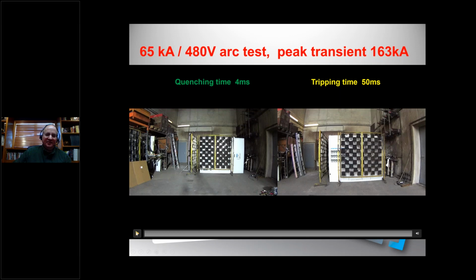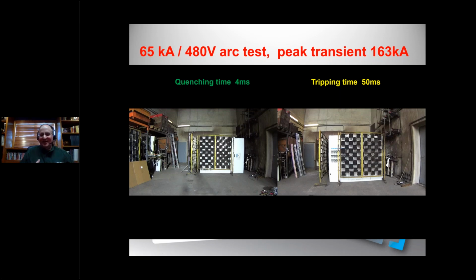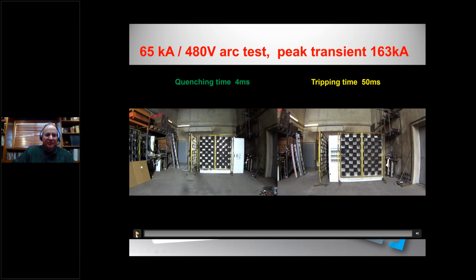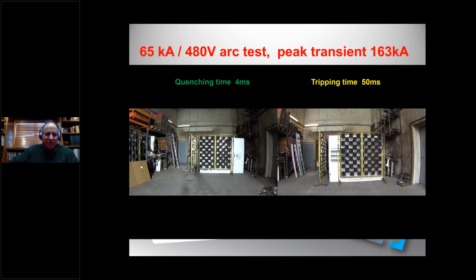For any of you who have been to my presentation before, I always like to show this slide because it shows the difference between standard type tested equipment and type tested equipment with an arc quencher. This is a 65,000 amp test at 480 volts on a UL891 listed switchboard. The switchboard on the left has an arc quencher installed. It has a quenching time of 4 milliseconds. The switchboard on the right does not have an arc quencher installed, but again, it is type tested.